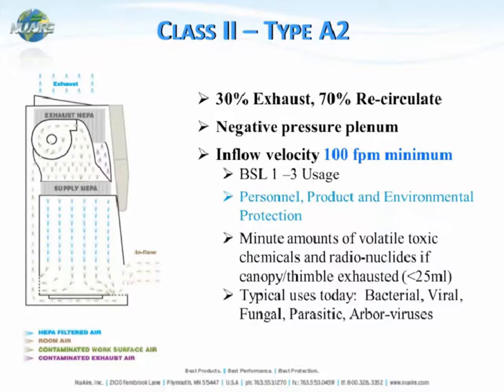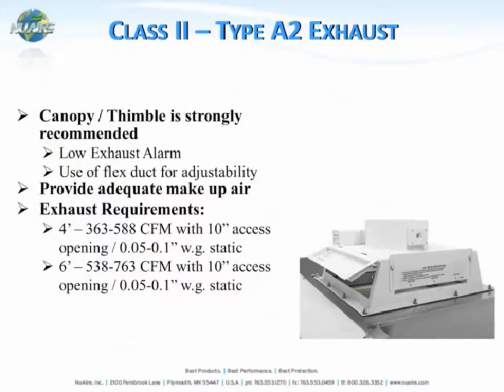An A2 cabinet gives you the ability to recirculate back into the room, which is very common. But if you are using some volatile toxic chemicals, you can exhaust to the outside. Exhaustion through an A2 cabinet is done by a canopy or thimble transition, and this is designed with a low airflow alarm. If the exhaust system has low airflow and is not able to exhaust the air to the outside, it will go into alarm to let users know that proper airflow is not being achieved.